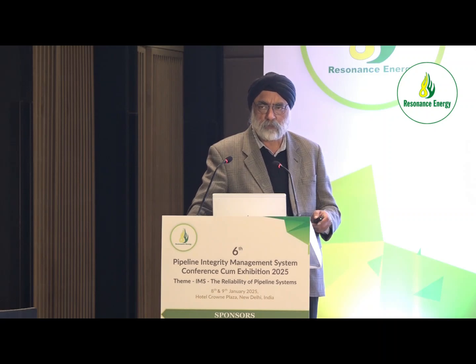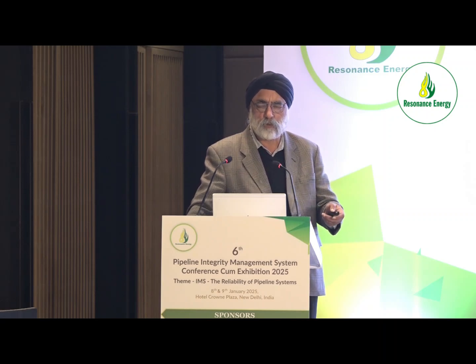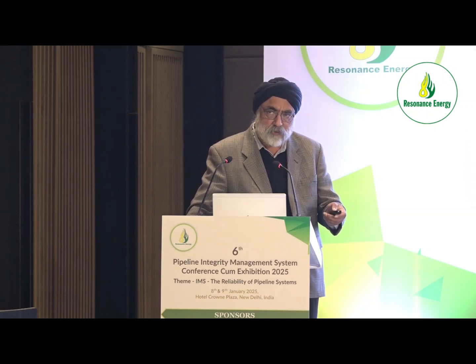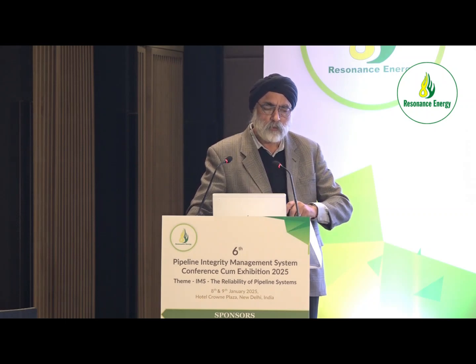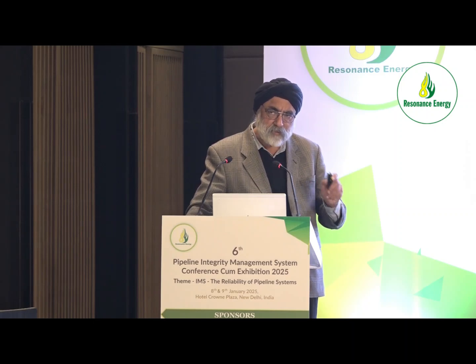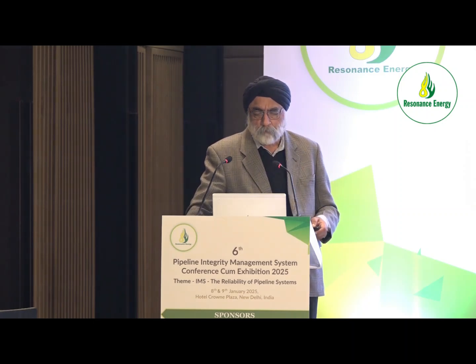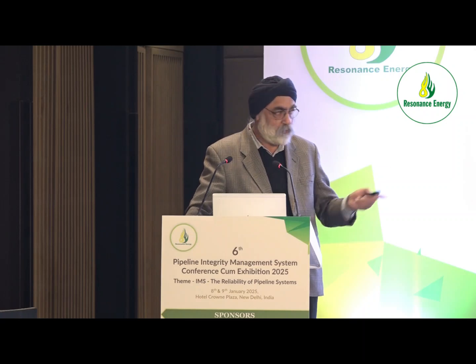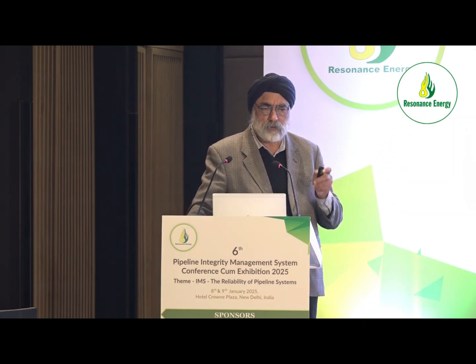So wherever I have damage, steel is in contact with soil, steel will corrode. The intensity of corrosion will depend upon the soil resistivity and the AC level on your pipe. This is what we try to avoid - small pitting on the pipes - because that's how pipelines are going to fail, and they do fail.